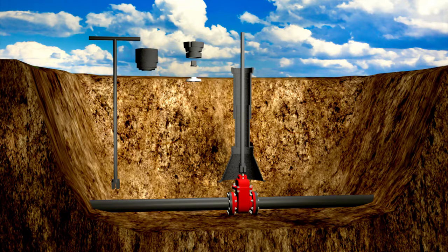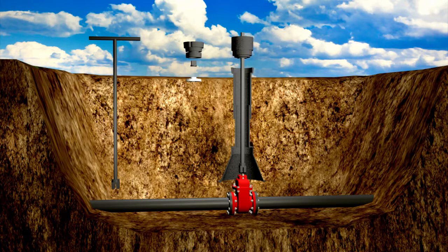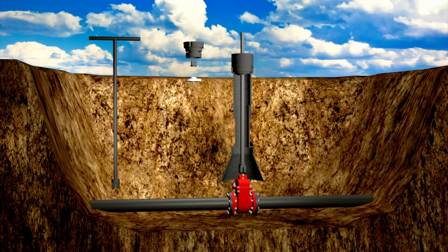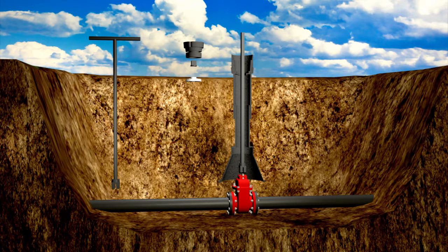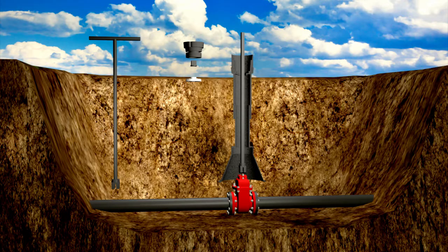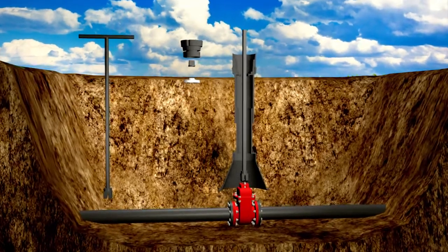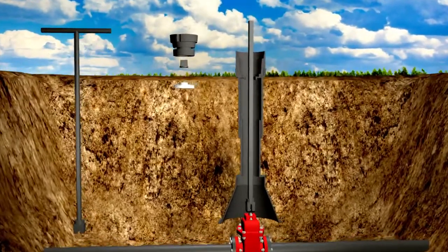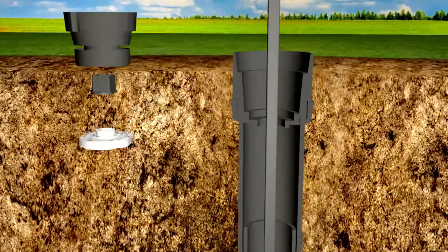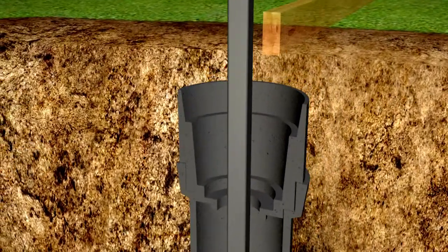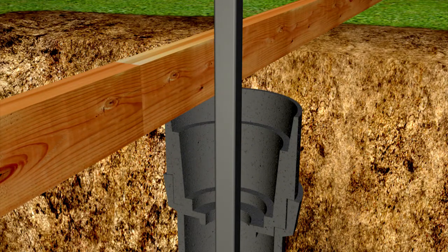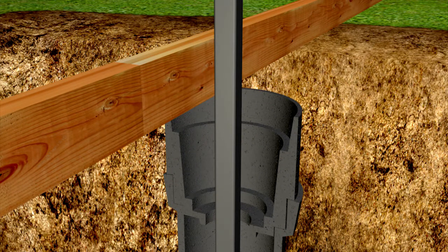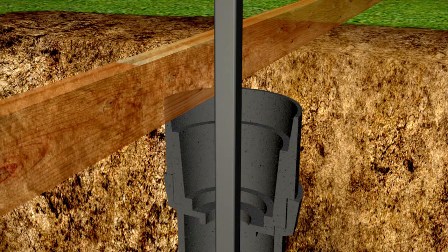Place the cast iron housing adapter over the extension stem and into the valve box top section. Then making sure that the top of the housing adapter is flush with the final grade, use a straight edge to mark the final grade line on the extension stem.